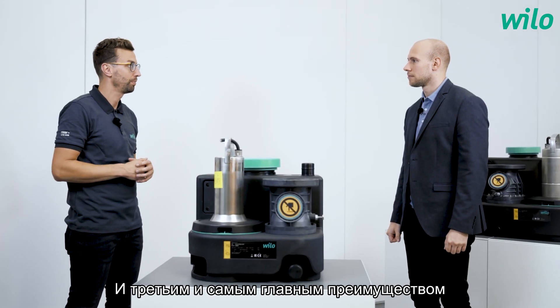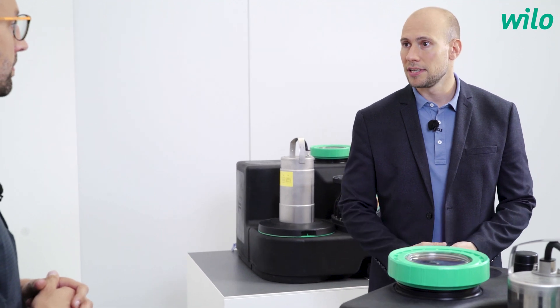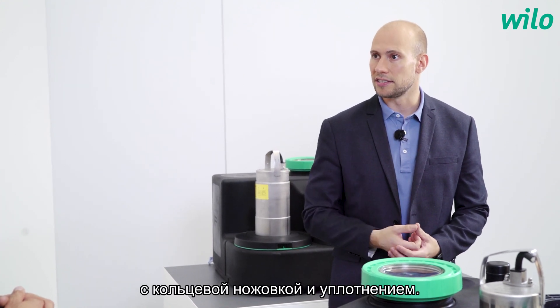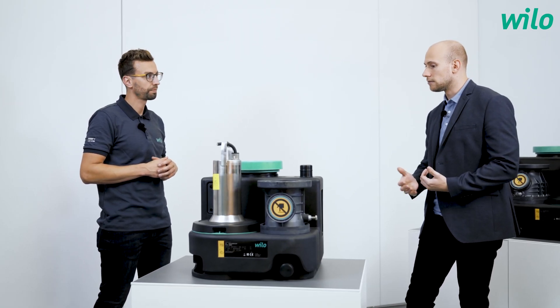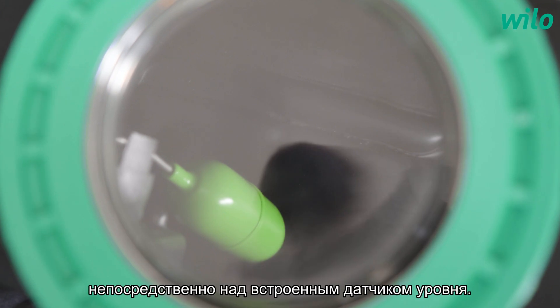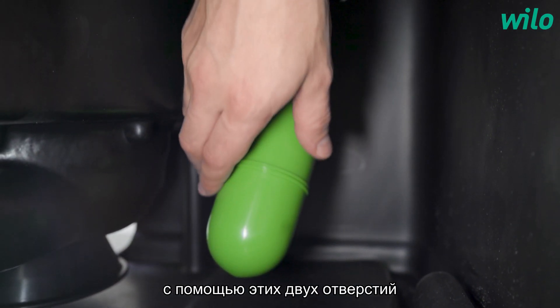The third and most important benefit is for the plumber — service and maintenance. Overall, the installation must be very flexible. We have three selectable inflow areas around the whole tank, and included in the scope of supply is a circle saw and the necessary lip sealing. So the plumber can create the inflow wherever needed in the specific surrounding. Regarding servicing and maintenance, we have inspection holes, especially in the non-return valve as well as in the tank. We also have a transparent cover placed directly above the float switch, so you can do a very easy, hygienic, and quick visual check of the whole system without removing any parts.